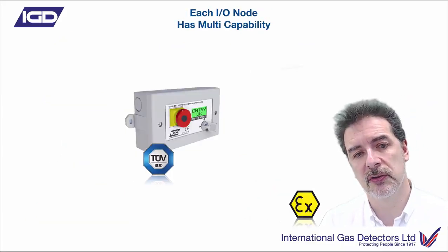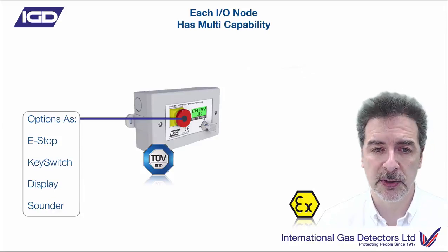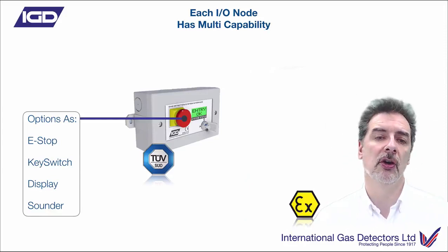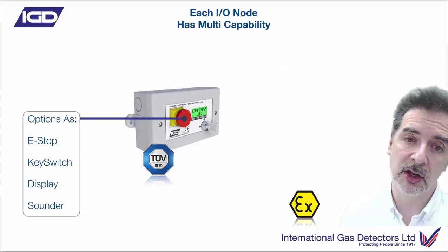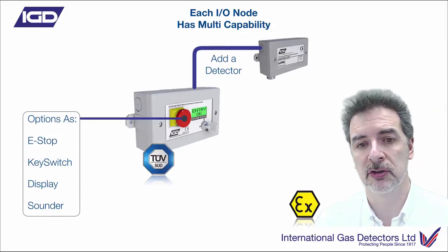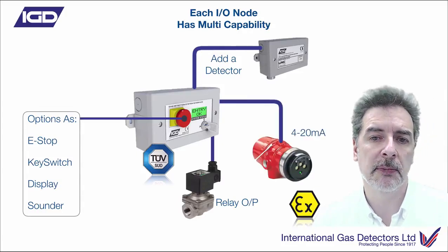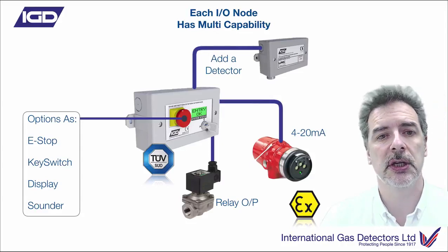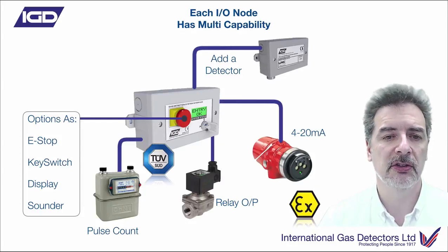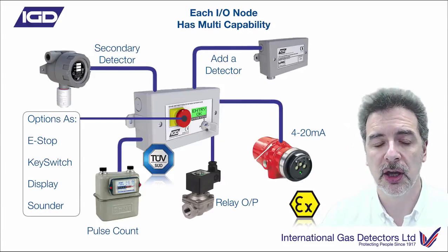The same is true of the annunciators. If you've got those on site, you've got options for e-stops or key switches, an RGB display you can program with custom text - very commonly used for door entry control or as an intelligent beacon sounder in a small room complex. You could add a flammable gas detector on there, use the relay output to control something, configure I/O points as 4-20mA analogue inputs to control another device, use pulse counting to totalize gas meter readings, or add a secondary detector - actually having two gas detectors connected off one door entry node.